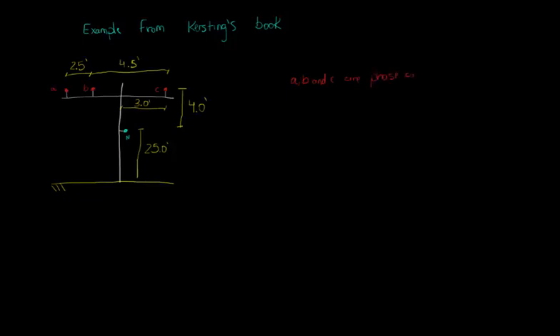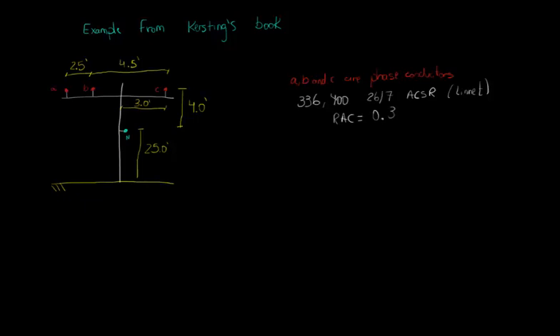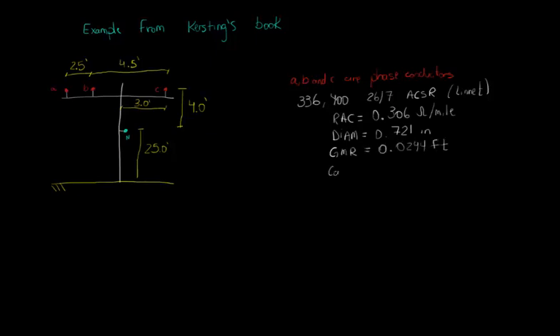The phase conductors are defined with a size of 336,400 stranding of 26 over 7. The material is ACSR and from the book's table in appendix A we can get that the AC resistance is equal to 0.306 ohms per mile. The diameter is equal to 0.721 inches and the geometric mean radius is equal to 0.0244 and the capacity is 530 amps.